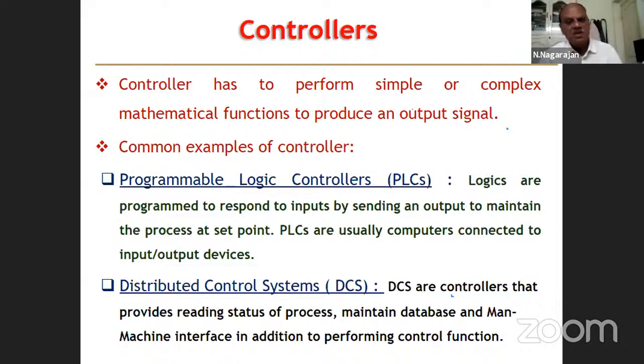Logics are programmed to respond to inputs by sending an output to maintain the process at set point. The logic is inbuilt, meaning the logic we write. Usually process engineers write the control logic, how to control the level in the vessel. That control logic is given to the instrument engineer, who will configure the logic in the PLC.